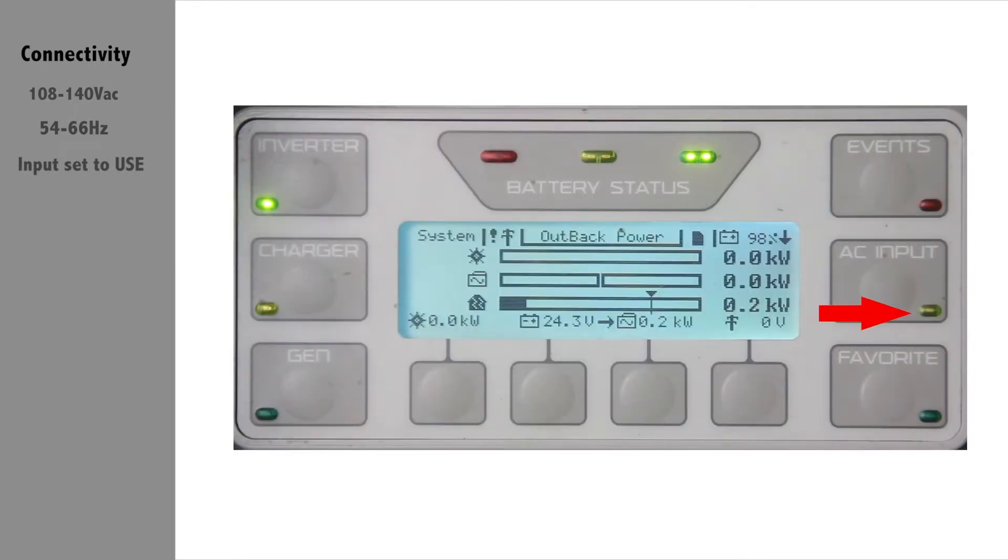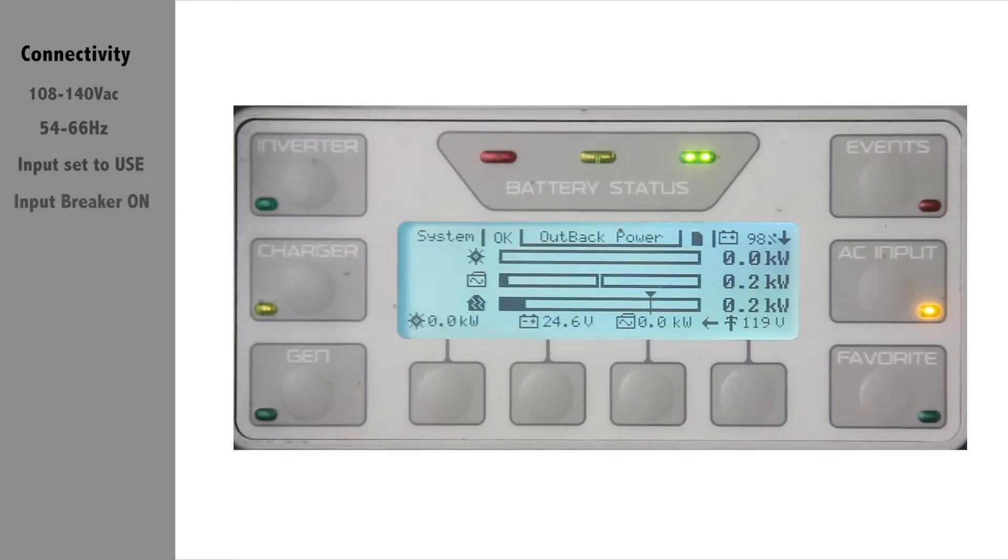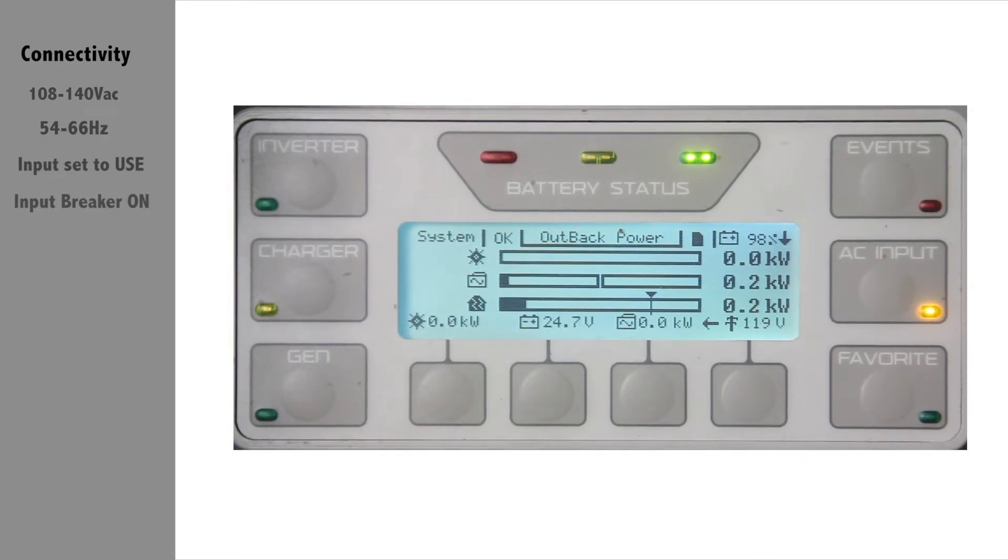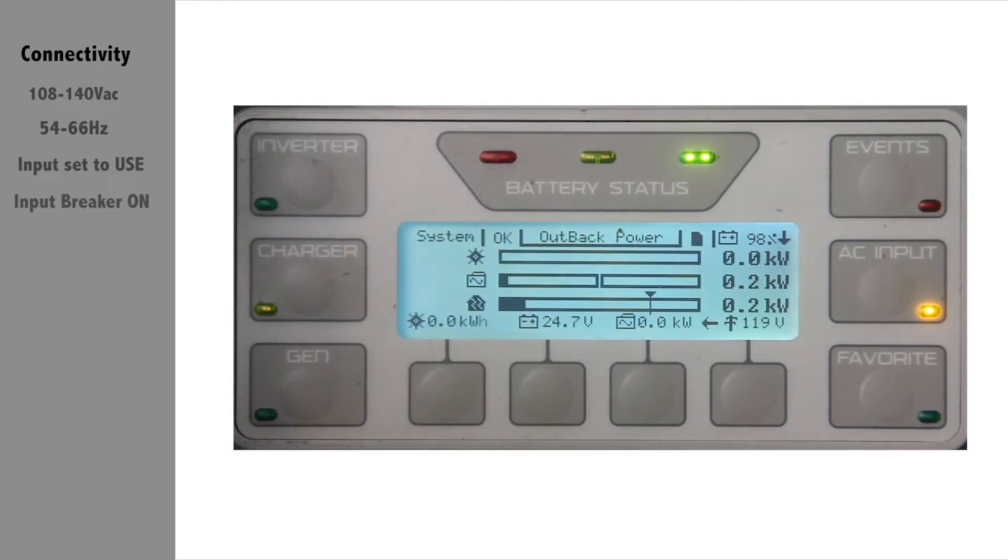If you do not see the AC input light at all, make sure your AC input breaker is turned on. If the source is rejected after previously being accepted, the inverter will go back to invert mode, and the AC input light will switch from solid to flashing.